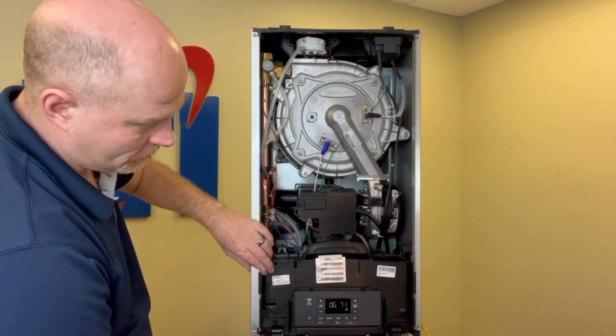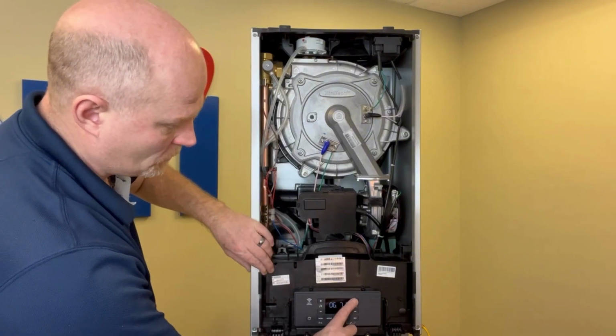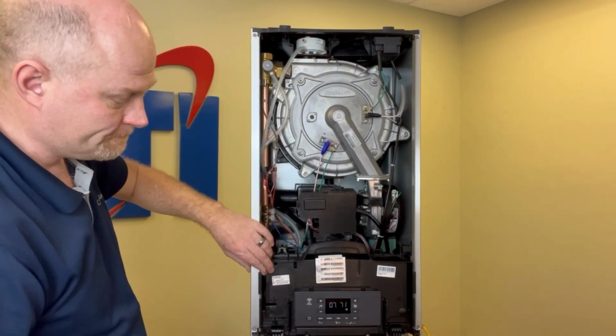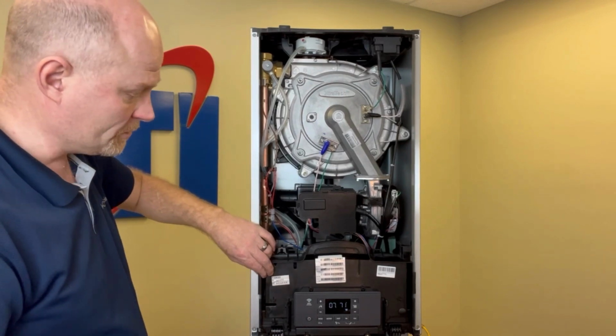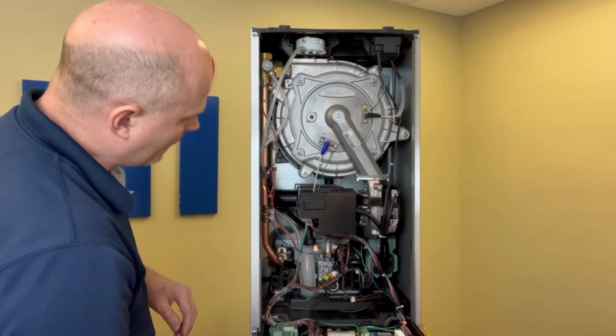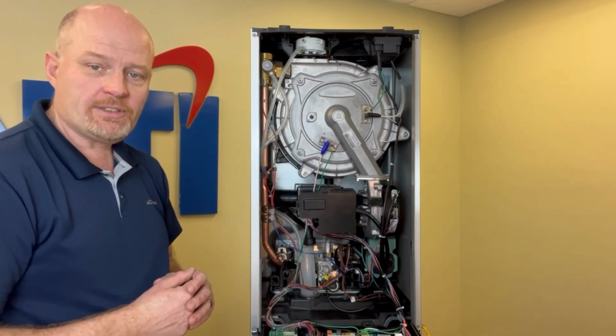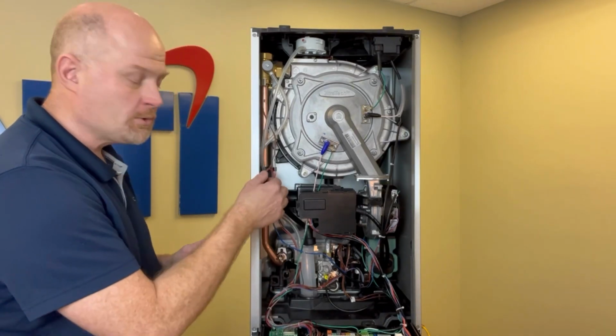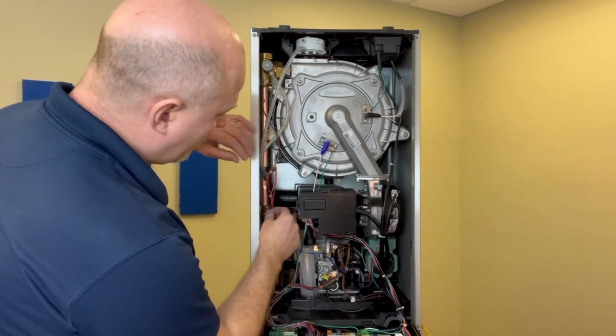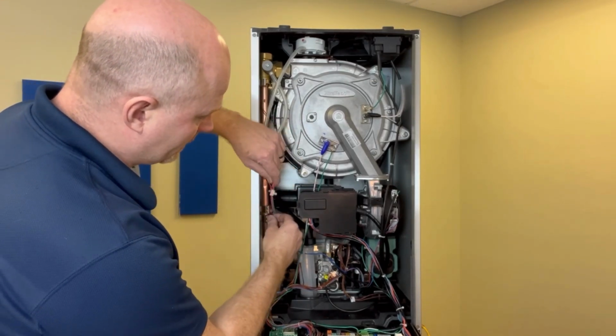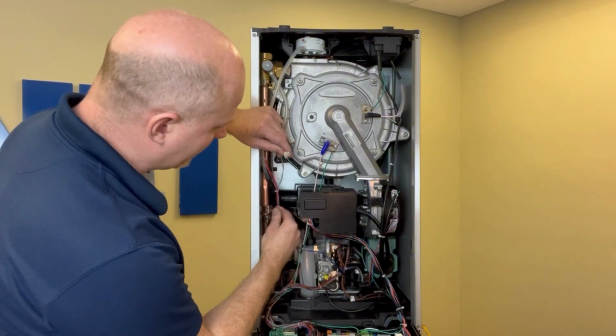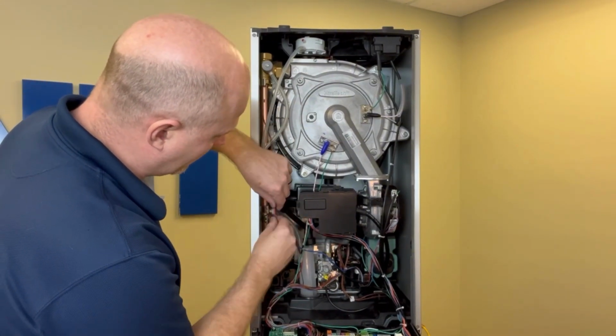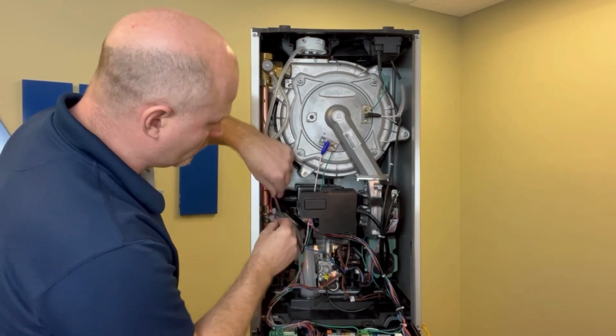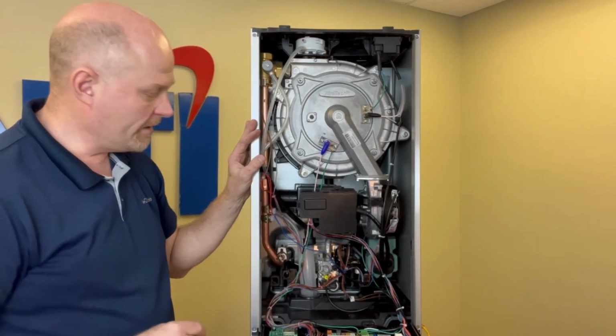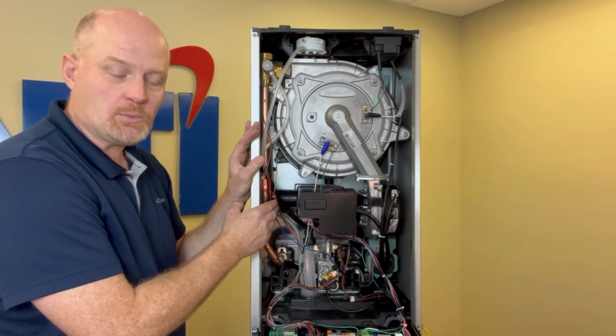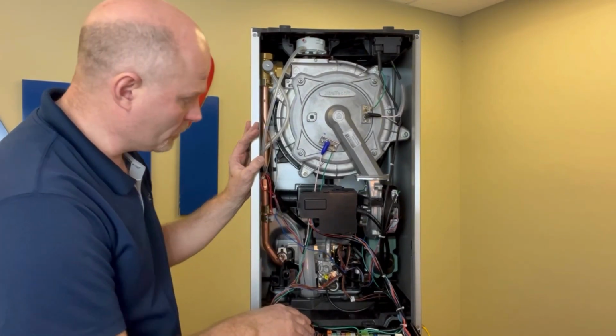And what we see is that our outlet sensor, the red wires, is at 71. If we hit plus to see the inlet sensor, it's also at 71. So these sensors appear to be working correctly. If you had a mismatch between the sensors, that mismatch might be because you have a bad sensor or possibly a wire harness. In order to test that, leave the sensors in the same positions, take the two wires and switch the wires back and forth and see if the problem follows the sensor or follows the wire. If the problem follows the wire, you may have a damaged wire harness or possibly a damaged circuit board.